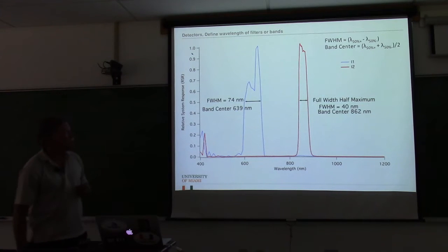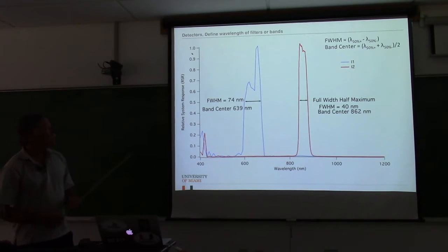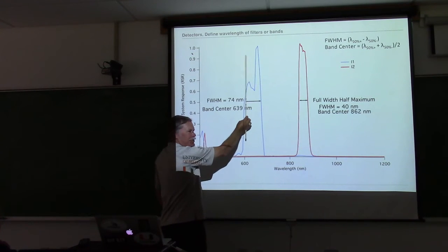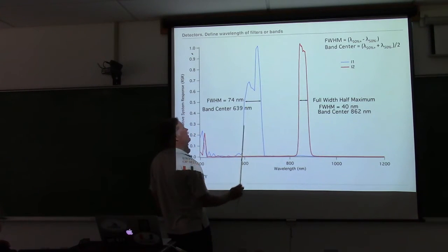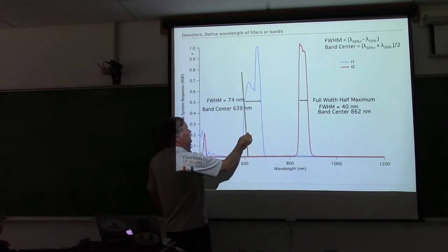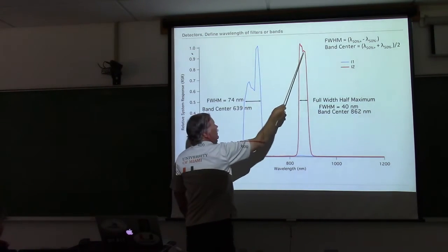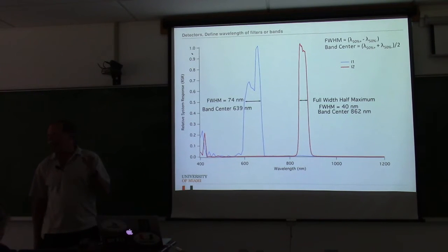And then when you try to choose what wavelength that filter represents, we don't use the peak, because in general these things are really screwy looking for interference filters or whatever. They're not just a nice Gaussian or a nice square peak. They have these weird structures in them, so by picking a peak you can get a bad number for the wavelength.